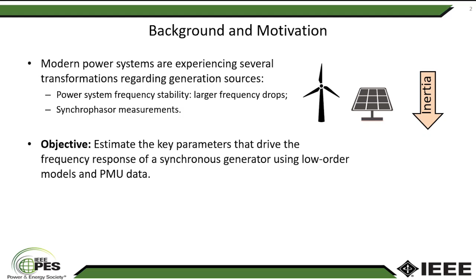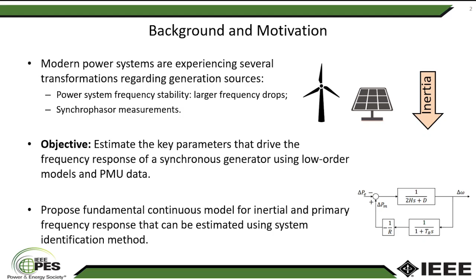In this context, the main objective is to estimate the key parameters that drive the frequency response of synchronous generators, using PMU measurements after disturbance. Based on this measurement data and an underlying frequency response model, the generator's inertia and damping and the turbine governor parameters can be properly estimated using a system identification approach.